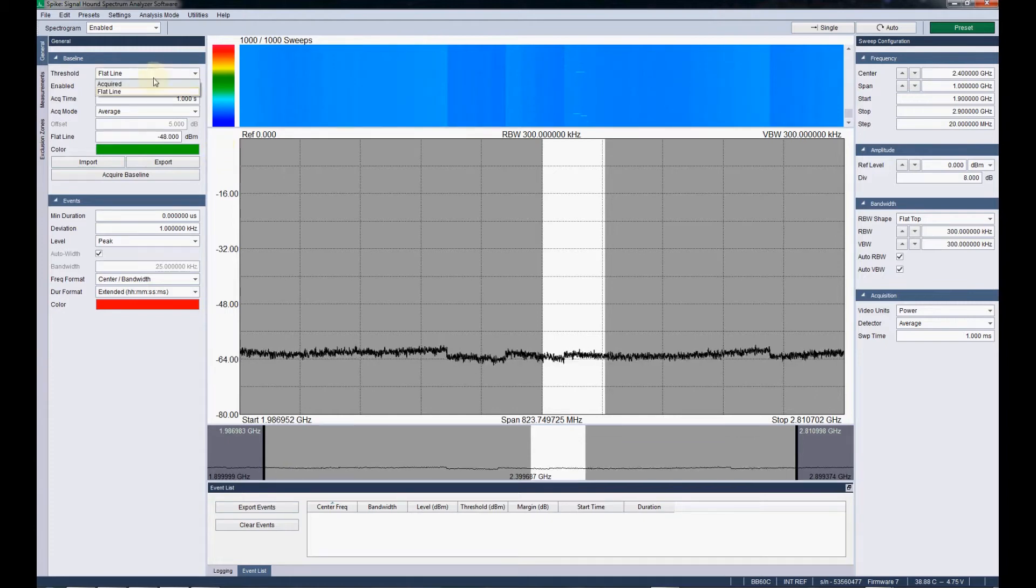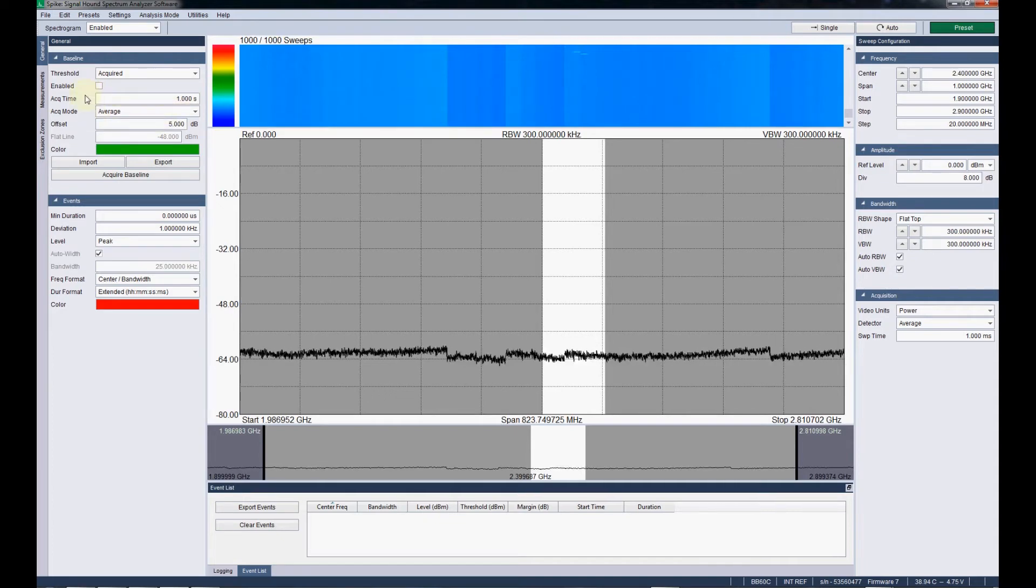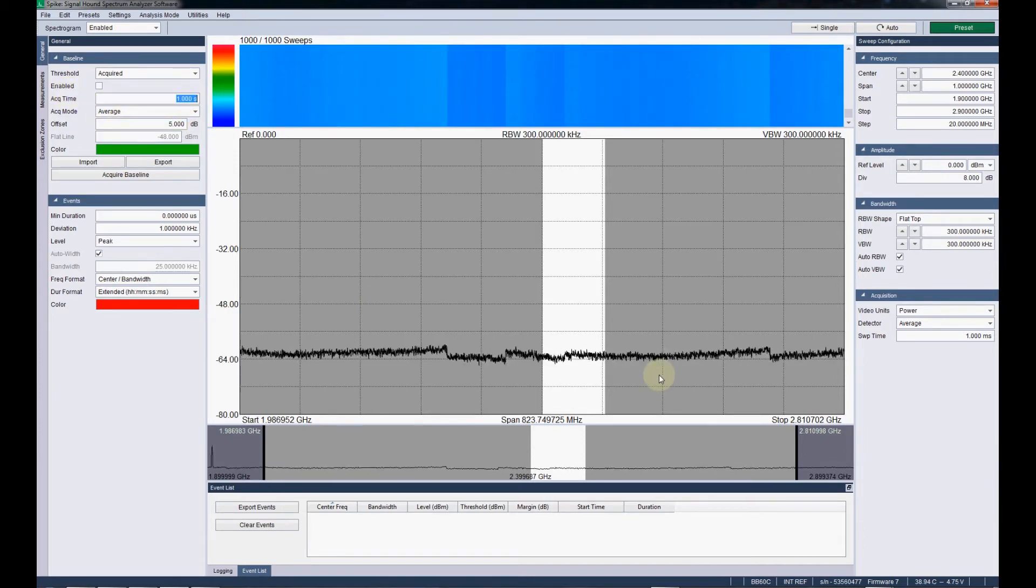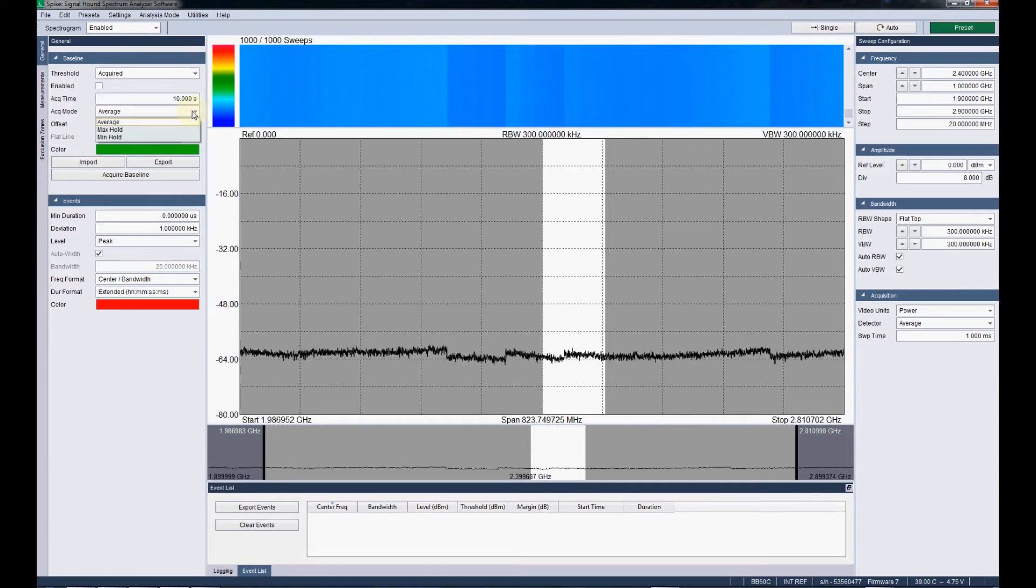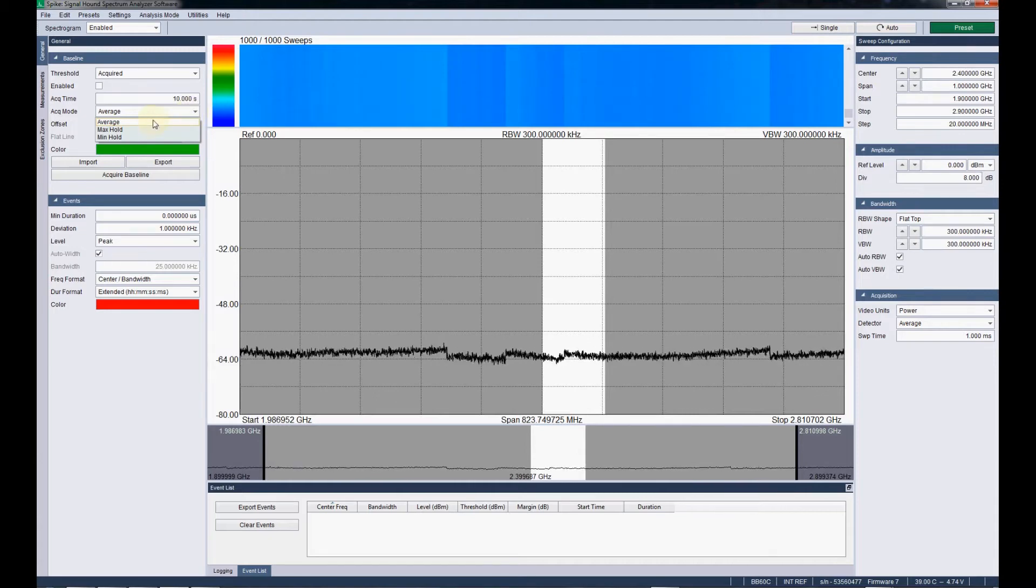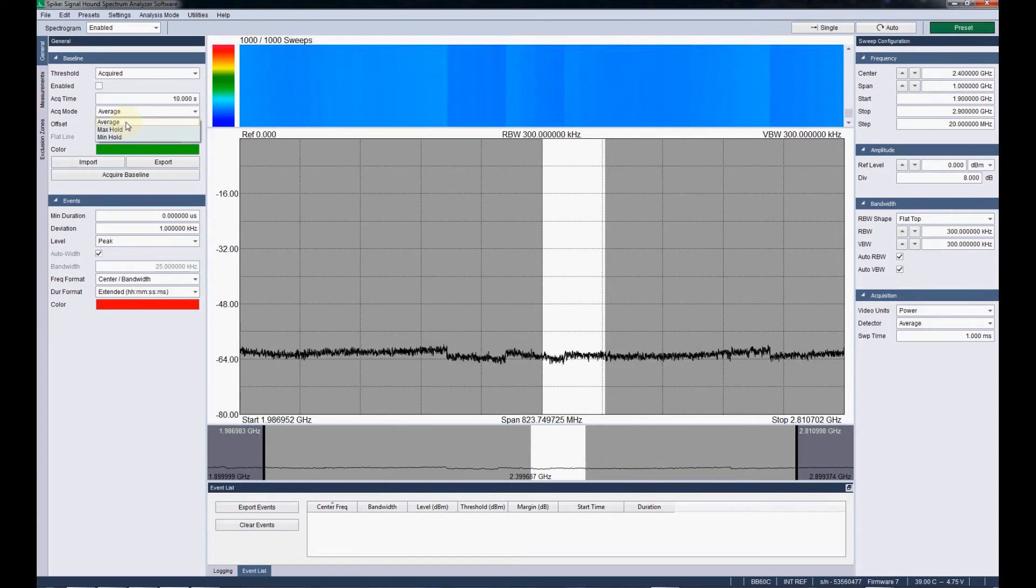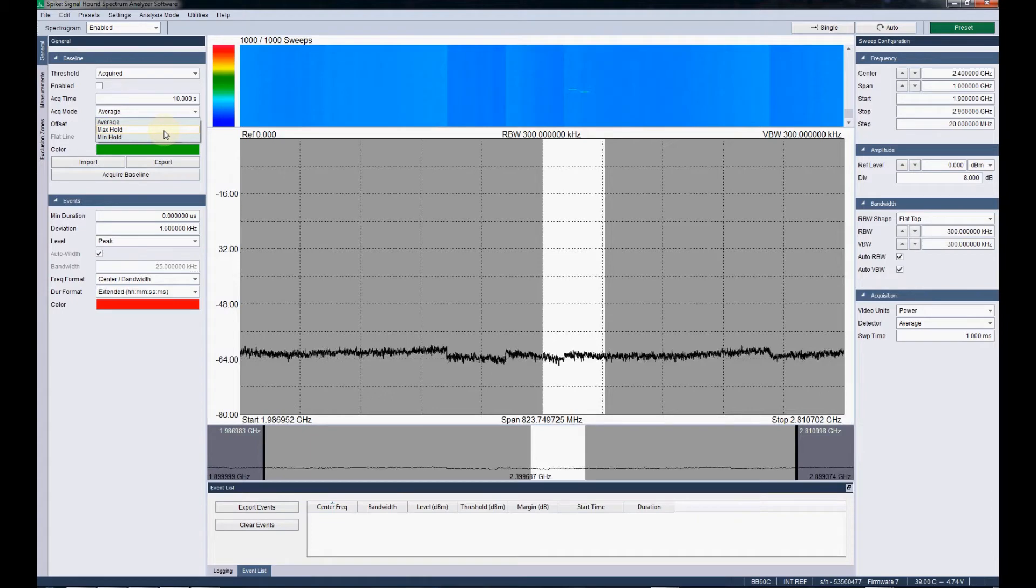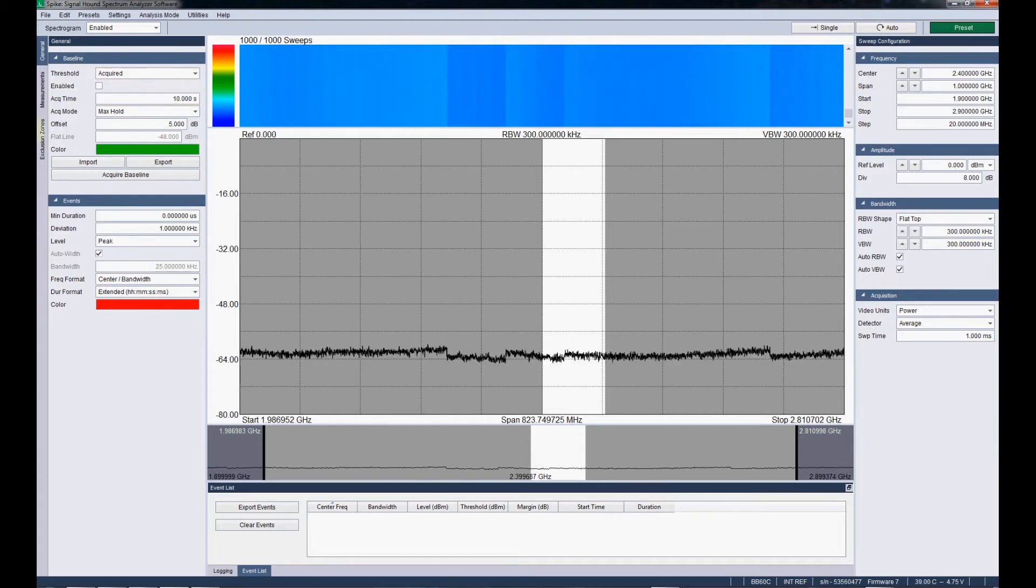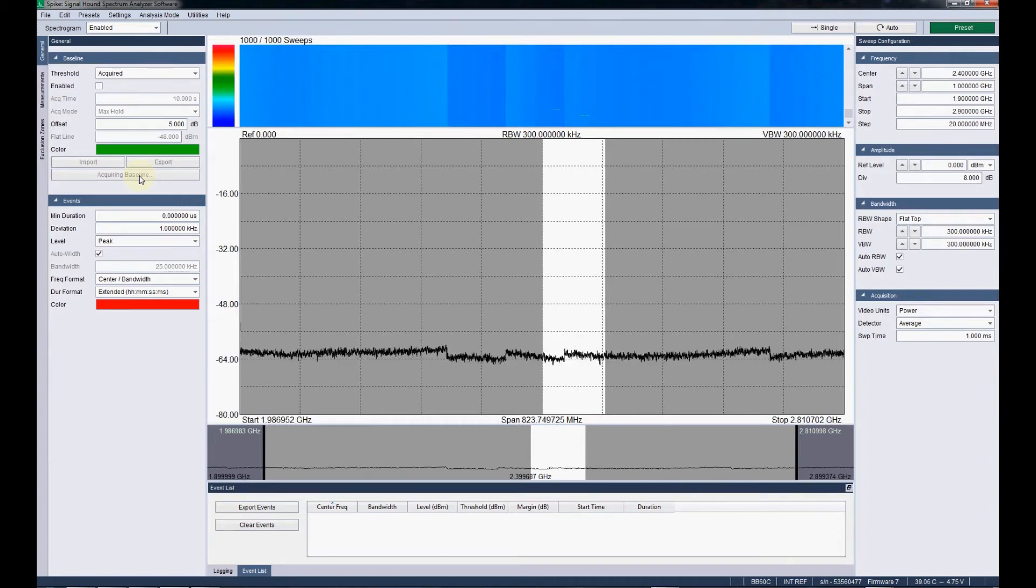Because that's the more interesting type of baseline. These settings have to do with how a baseline is acquired. It's going to be acquired over a period of time. Let's kick this up to like, I don't know, 10 seconds. And the acquisition mode is going to be kind of what kind of accumulation function it's going to use while it's acquiring the baseline. Average, it's just going to be an average of all the sweeps that occur during that time period while it's acquiring. And then max hold and min hold. Let's do a max hold for 10 seconds. And now we just hit acquire baseline. And we'll wait 10 seconds.